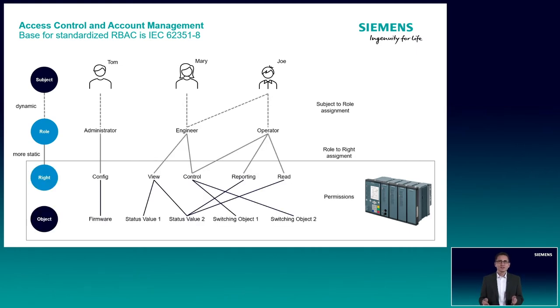Each role is granted specific rights on specific objects in the target device, and this role-to-right assignment is static and is implemented inside the IED. Let's look at the example. User Tom has the job role administrator, which grants him the right to configure the firmware in the IED. This allows him, for example, to install a new firmware version on the IED.